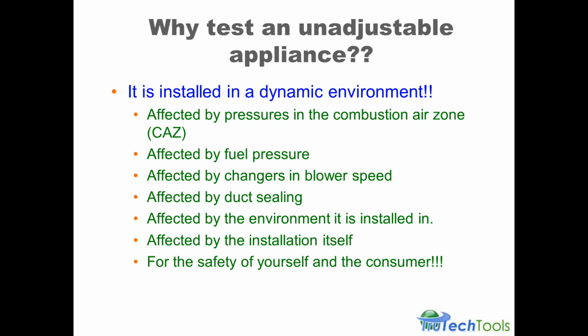I've seen firsthand fuel pressure changes and fuel quality changes at the AGA labs, which can lead to variations in the way the combustion equipment operates. There can be changes in settings of blower speeds for various reasons. Either technicians or owners can change the blower speed, which would change the way the heat is extracted off the heat exchanger, which can change the way the appliance operates. Duct sealing can affect the available air flowing into the combustion air zone. Anything in the environment itself, including cleaners or paints or paint thinners, can get into the airstream in an atmospheric system and then start to corrode or rot or interfere with the way the system performs. And even the installation itself, if it's not done correctly, with the correct airflow over the heat exchanger and the correct fuel pressure, can compromise the way the equipment is intended to operate. All this is really for the safety and the performance for yourself and for the consumer.